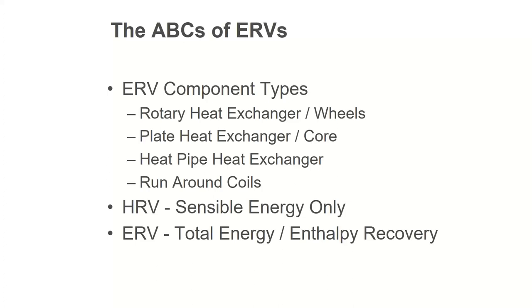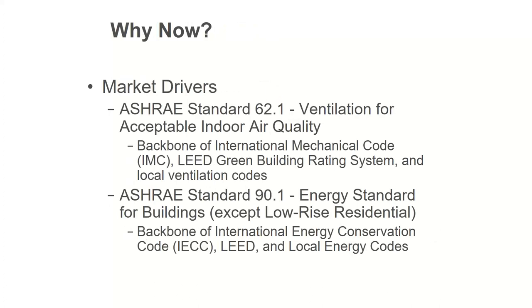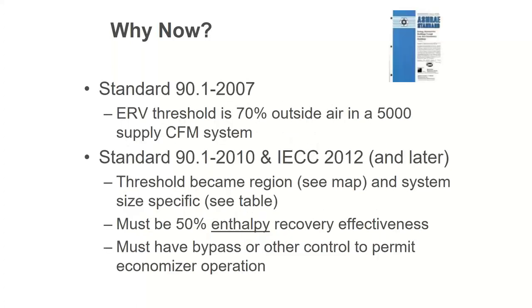I want to save the moisture in the winter. I want to get rid of the moisture in the summer. ASHRAE 62 is a driving factor. It dictates our ventilation rates, as we mentioned. ASHRAE 90.1 is the other driving factor behind ERVs. In many cases, they are code required on newer systems.